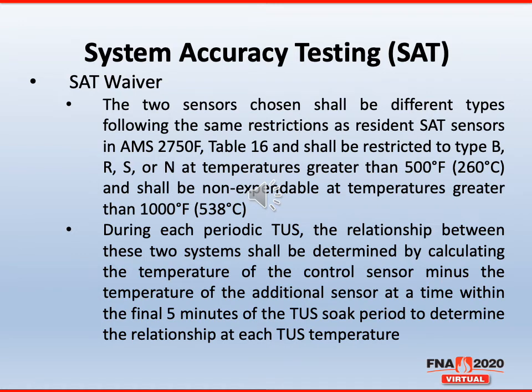Lastly, along with the waivers, the 2 sensors chosen shall be different types following the same restrictions as the resident SAT sensors in AMS 2750 Table 16, and shall be restricted to types B, R, S, or N at temperatures greater than 500, and shall be non-expendable at temperatures greater than 1000 degrees Fahrenheit. During each periodic TUS, that relationship between these 2 systems shall be determined by calculating the temperature of the control sensor minus the temperature of an additional sensor at a time within the final minutes of the TUS soak period to determine the relationship at each TUS temperature. This is where you get your relationship that stays within the 2 degrees between the 2 existing sensors.